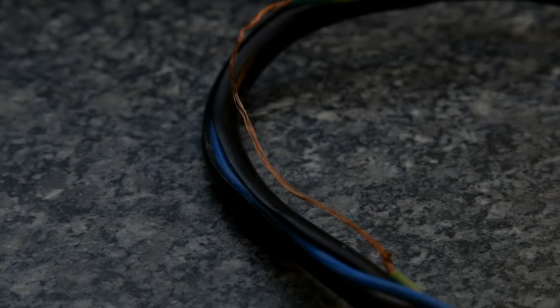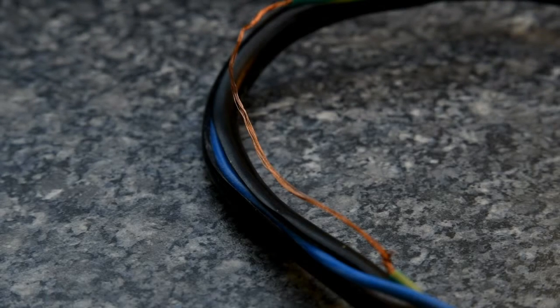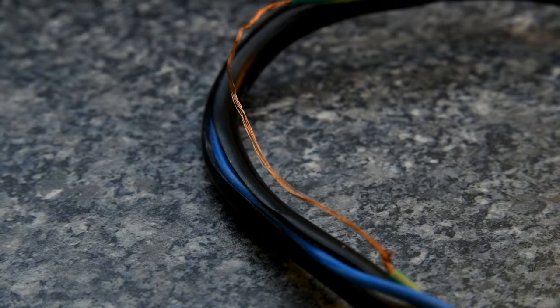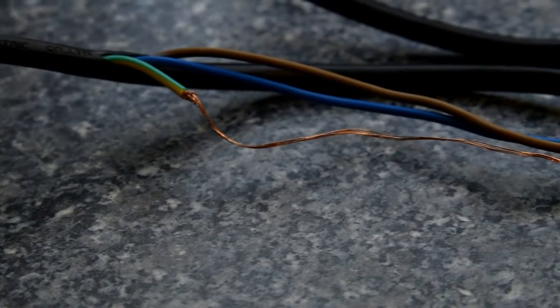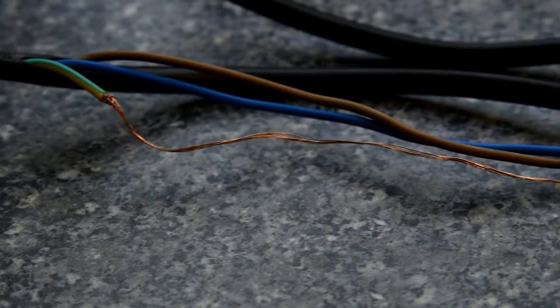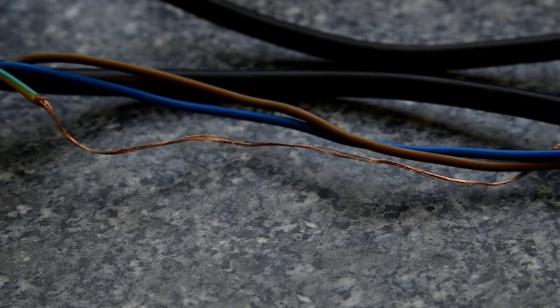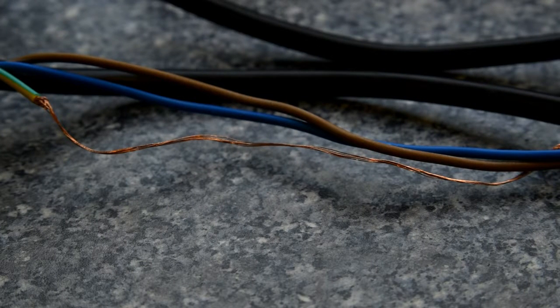Here's our soft test. Passes just fine. No sweep. Despite the extensive damage, the test has passed it because it isn't really testing the strength and integrity of the earth wire.